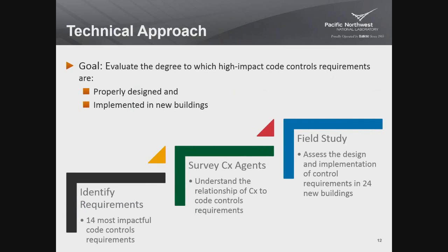So for the project that we did, our goal was to evaluate the degree to which high-impact control requirements are properly designed and implemented in new buildings. And we took a three-step approach to do this. The first thing we did was to identify the most impactful requirements, and we drew the line at 14. That was about what we thought we could handle in this study, so we took the top 14. We did a survey of commissioning agents to understand the relationship between commissioning and code-required controls. And then we did a field study where we assessed the design and implementation of those code-required controls in 24 new buildings.